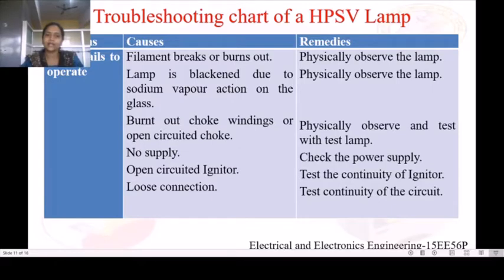Next, the lamp is blackened due to sodium vapor action on the glass. For this cause also, we need to physically observe the lamp to see whether it is burned out or not. Then, burnt out choke windings or open circuited choke. For this, physically observe the choke, and it can also be tested using a series test lamp for any open circuit or short circuit. If the test lamp glows dim, we say that the choke is in good condition. If the test lamp glows brighter, we say that there is a short circuit in the choke.